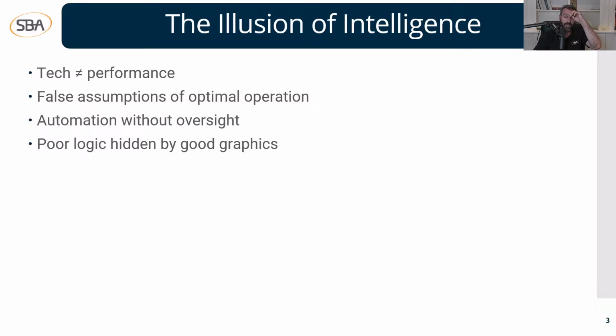Same thing goes for 'set it and forget it'—it only works when the system is properly set up. Just because you set a set point during startup doesn't mean it will still work 2 or 5 years down the road. You could have different tenants in the building with different hours of operation, or maybe there's a remodel with different criteria.